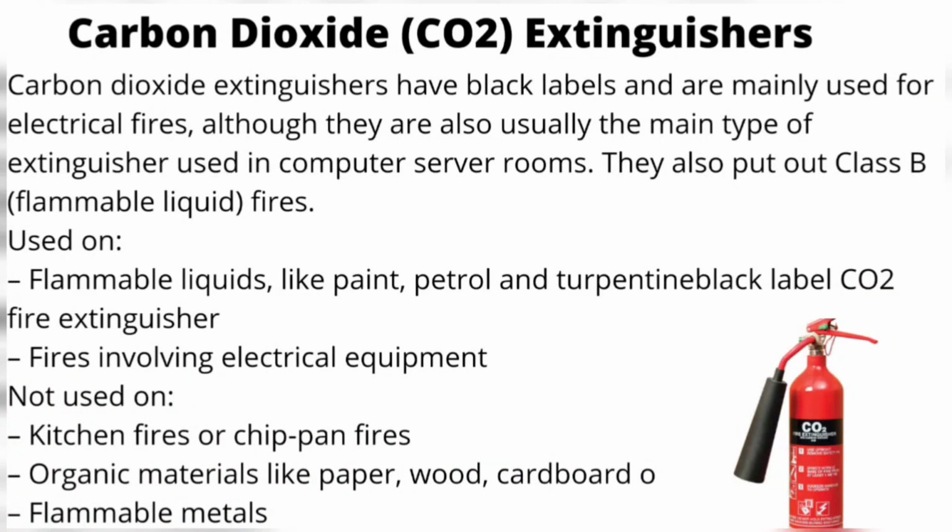Carbon dioxide, CO2 extinguishers. CO2 extinguishers have black labels and are mainly used for electrical fires, although they are also usually the main type of extinguisher used in computer server rooms. They also put out Class B flammable liquid fires. Used on flammable liquids like paint, petrol and turpentine.